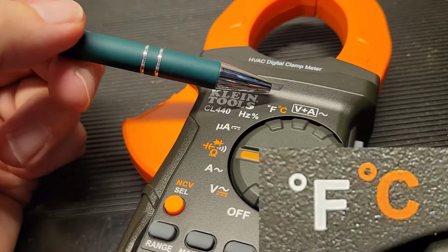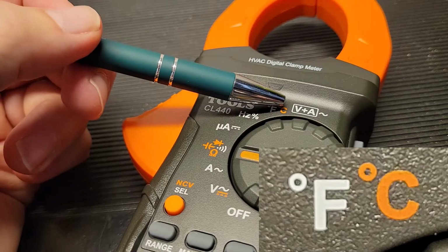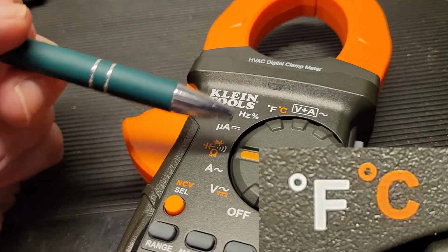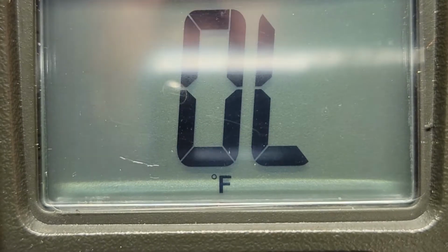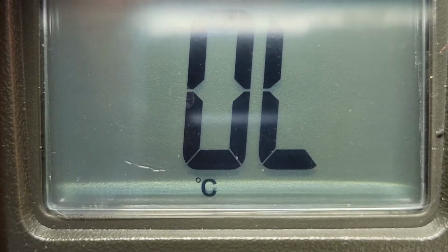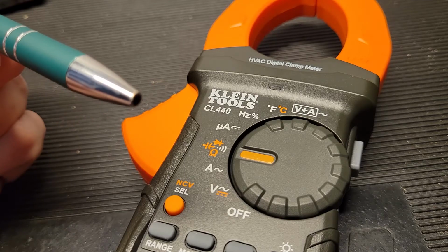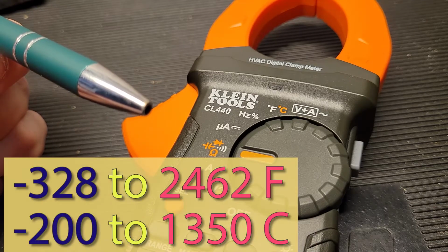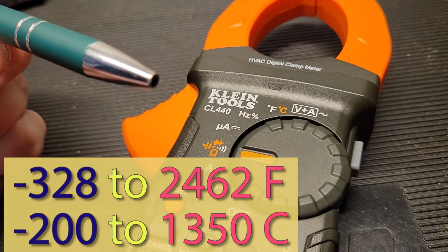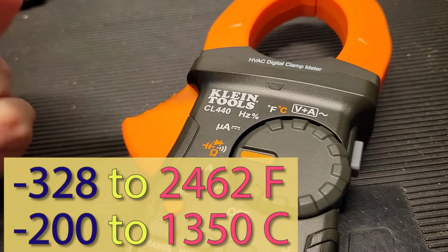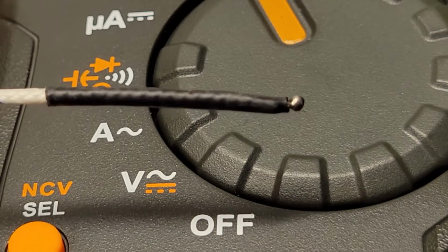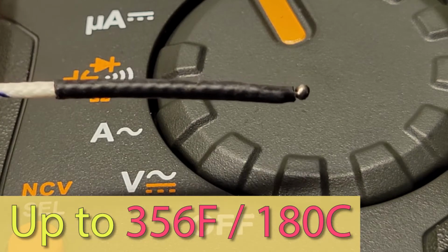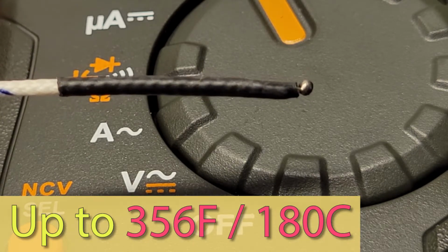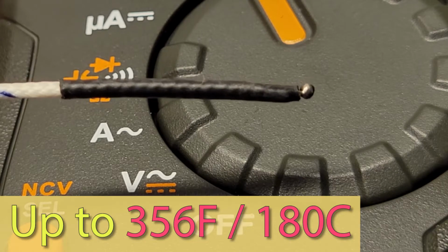Above that, we have F for Fahrenheit and C for Celsius. Again, the Celsius is orange, which means it'll be a function of pressing this button to get that particular reading. The unit is capable of reading temperatures from minus 328 degrees Fahrenheit to 2,462 degrees. But the caveat here is that your probe that's included with the kit can only go up to 356 degrees. And anything beyond that, you'll probably destroy the probe. So you need to get the appropriate probe for the temperature you're wanting to measure.